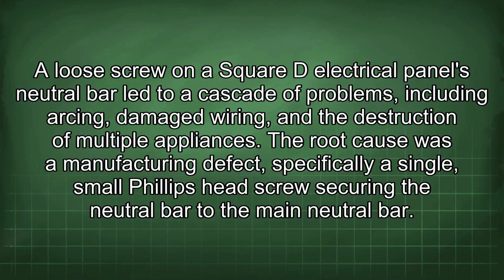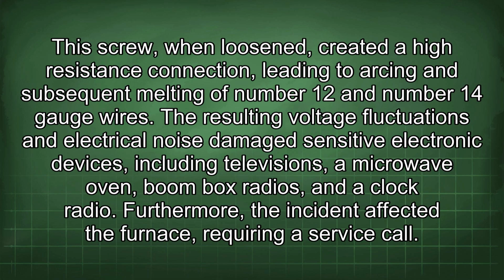A loose screw on a Square D electrical panel's neutral bar led to a cascade of problems, including arcing, damaged wiring, and the destruction of multiple appliances. The root cause was a manufacturing defect, specifically a single, small Phillips head screw securing the neutral bar to the main neutral bar. This screw, when loosened, created a high-resistance connection, leading to arcing and subsequent melting of number 12 and number 14 gauge wires.